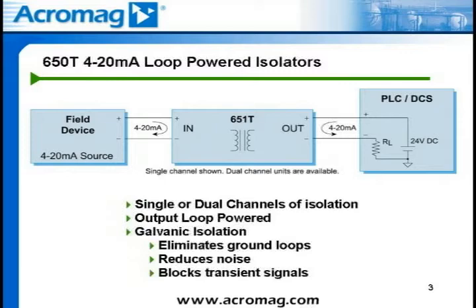Certain monitoring applications require tapping off an existing 4 to 20 milliamp DC loop to add a measuring or monitoring instrument. The 651T and 652T are ideal for this application because of the low 10-ohm input burden. If the isolator fails or loses power, it will not interfere with the existing 4 to 20 milliamp DC loop. The output of the isolated transmitter in this application can be wired to a field chart recorder or another PLC to enable redundant monitoring.